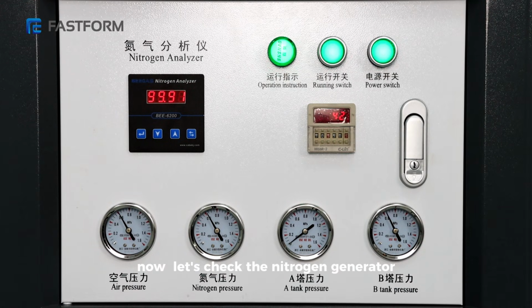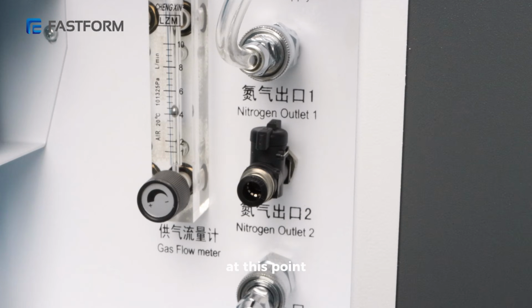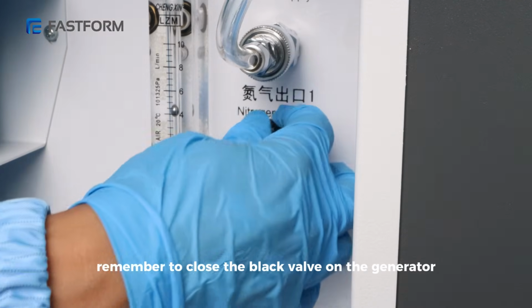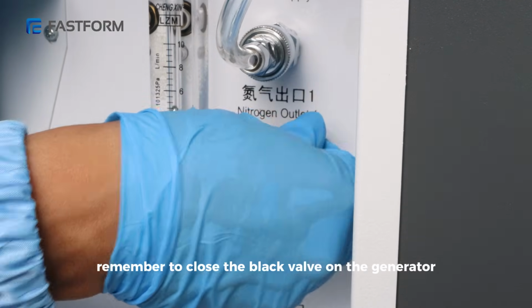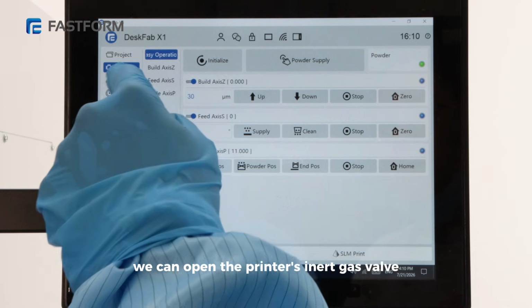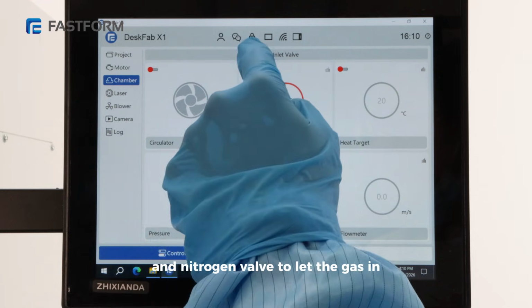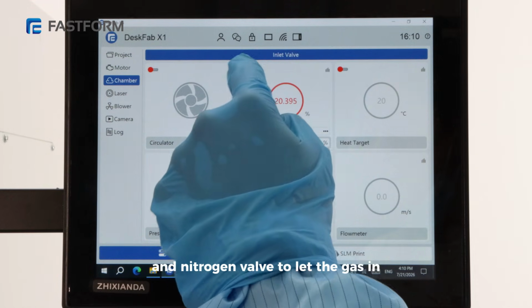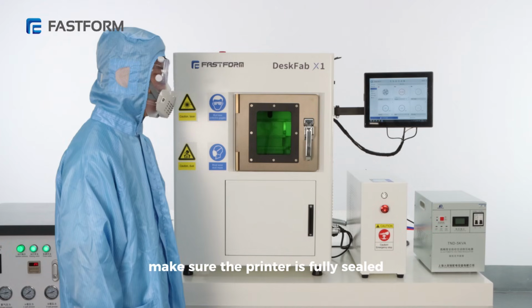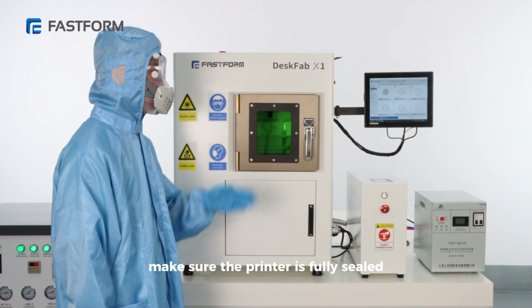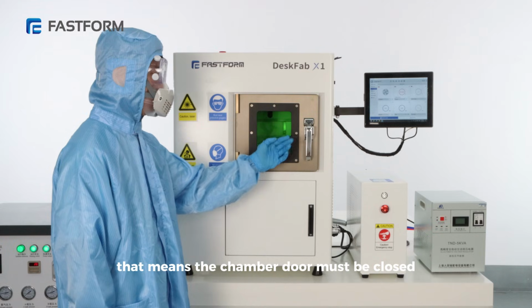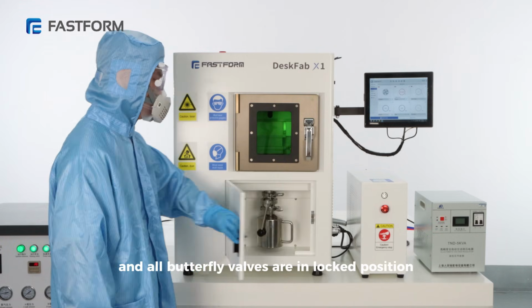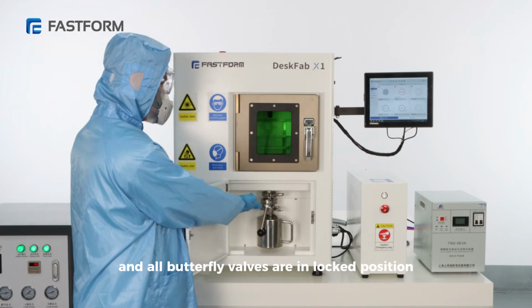Now let's check the nitrogen generator. The purity has reached 99.90%. At this point, remember to close the black valve on the generator. We can open the printer's inert gas valve to let the gas in. Before you do, make sure the printer is fully sealed. That means the chamber door must be closed and all butterfly valves are in locked position.